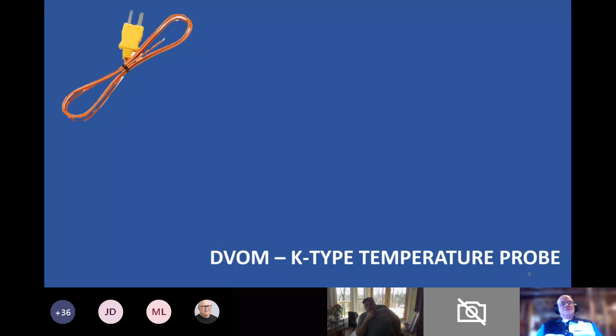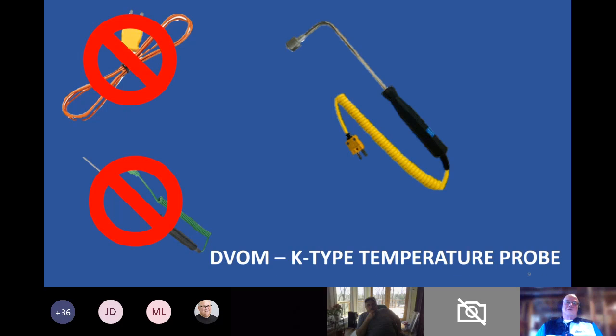So this is the immersion probe that comes with many DVOMs. I suggest not using that. It's not designed for a contact surface. This is a narrow, real skinny contact probe. I suggest not using either one of those. This is the one that I use, and it's merely a contact temperature probe, but it has about a 1/2 inch diameter contact surface, which will give you a very accurate probe temperature of that spot you're touching. It wants to be clean, no grease or crud buildup on it, and you'll get an accurate reading.